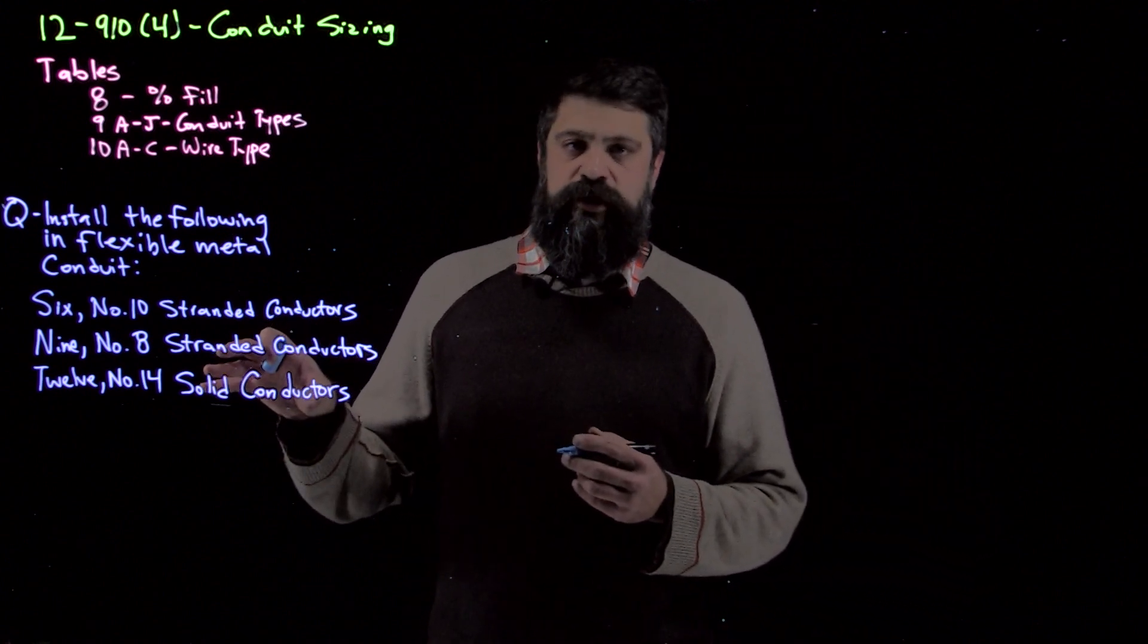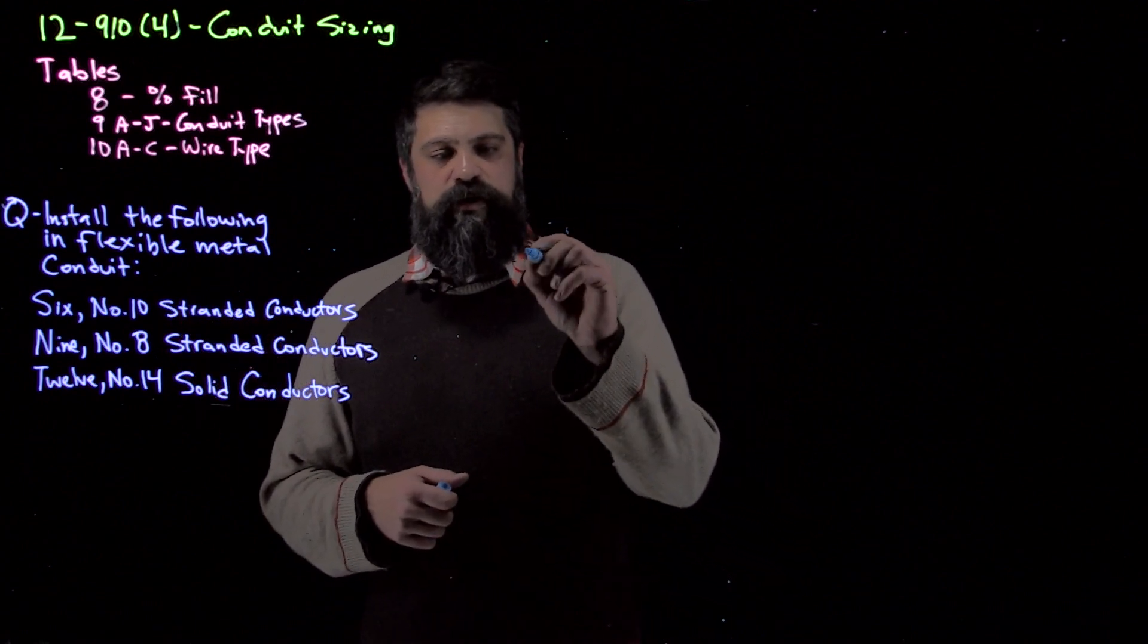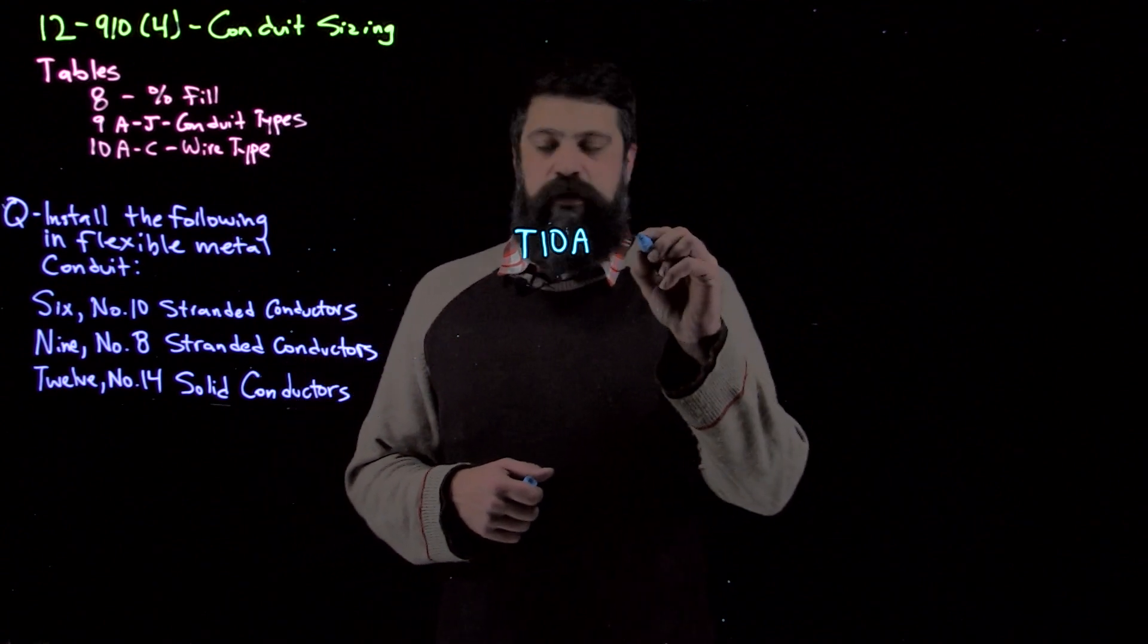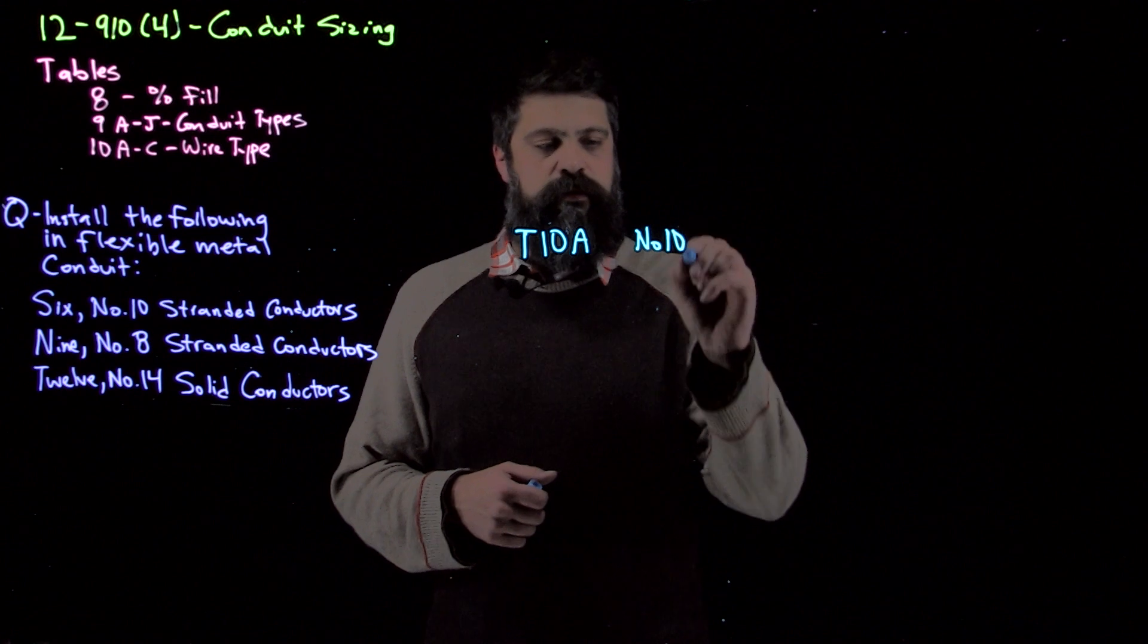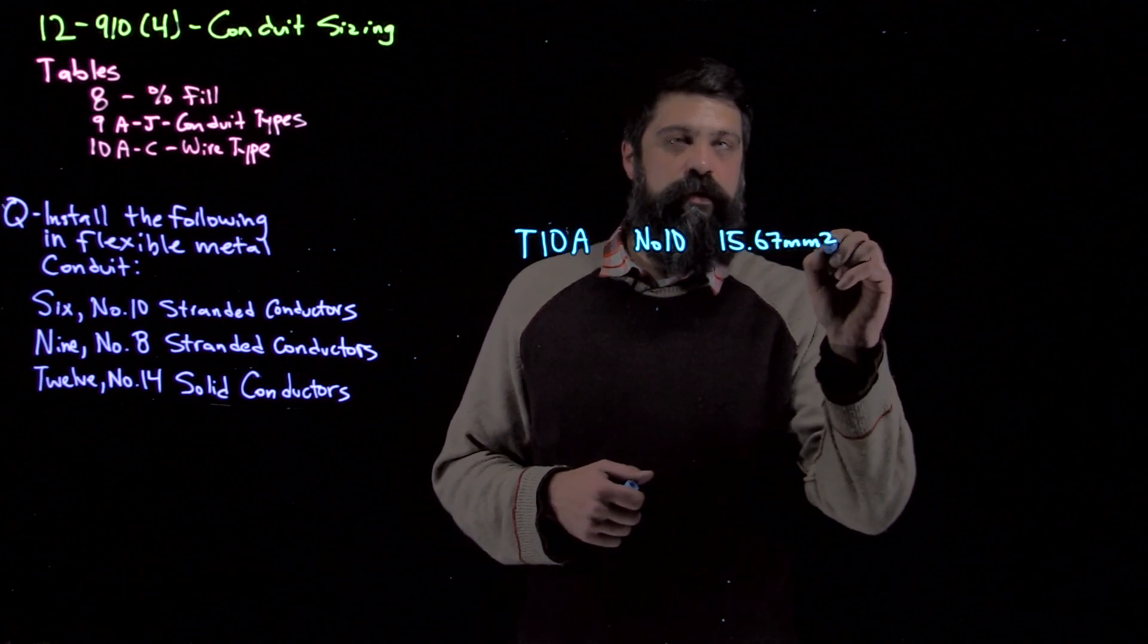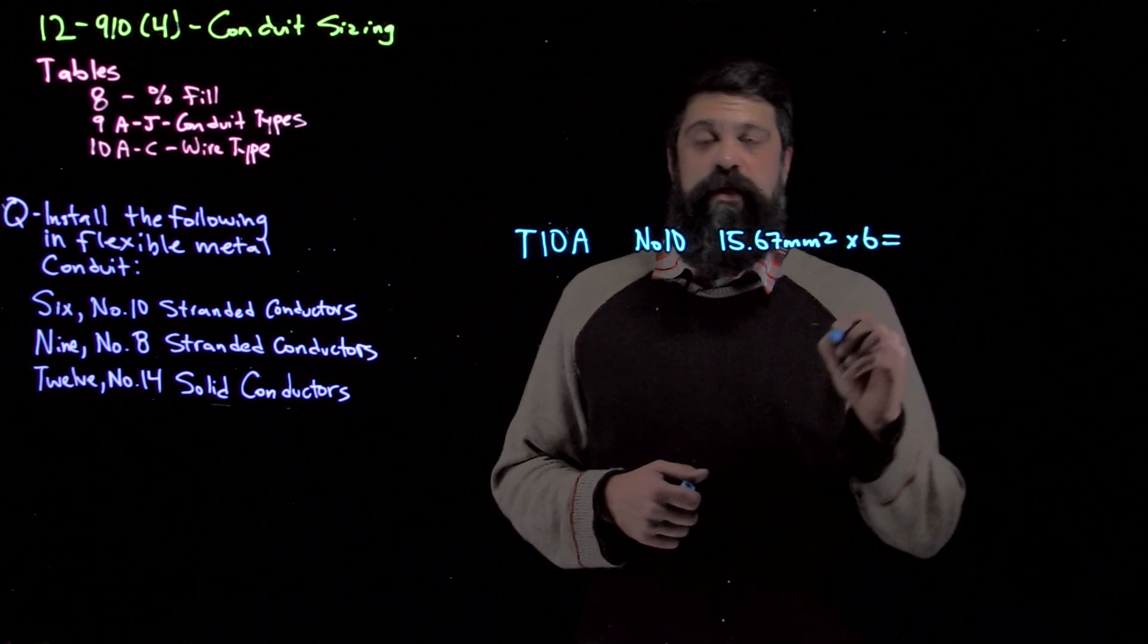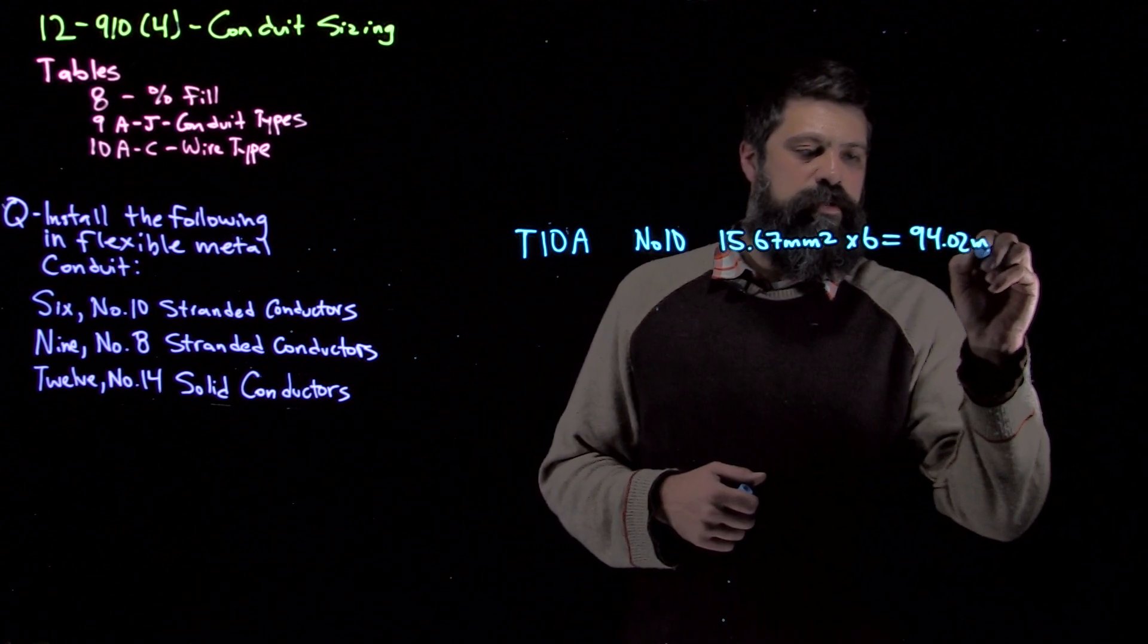So to figure out how much area these all take up, we'll start off with the number 10 stranded. So that's going to take us over to table 10A. And for a number 10 stranded conductor, I'm going to have an area of 15.67 mm². We have six of them. So when we multiply that all out, we end up with 94.02 mm².